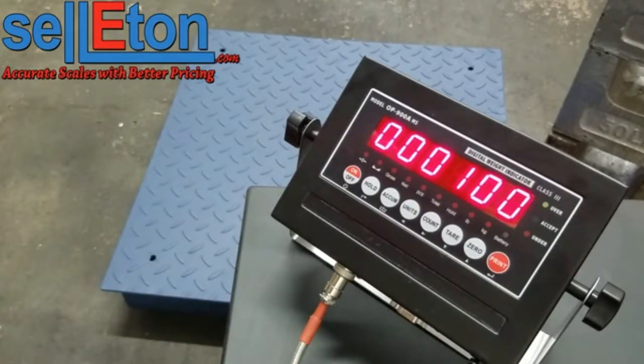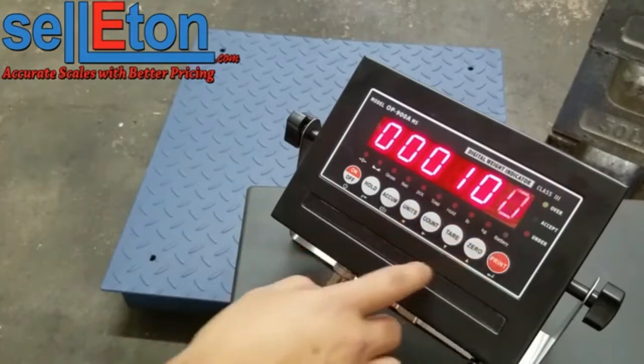Here we would enter how many pounds we're using to calibrate the scale. The OP-900A is recommended to use at least 10% of the max capacity when calibrating. In some cases you could use lower weights, but it's definitely recommended - the higher weight you have, the better calibration results you get, since you're setting higher frequencies. So here we would choose 100 pounds.